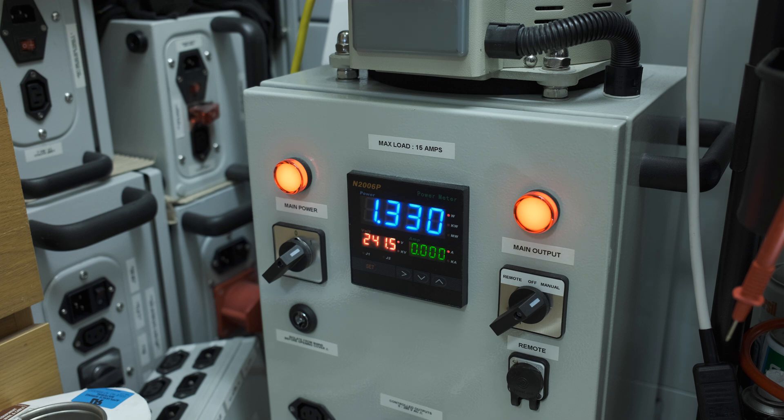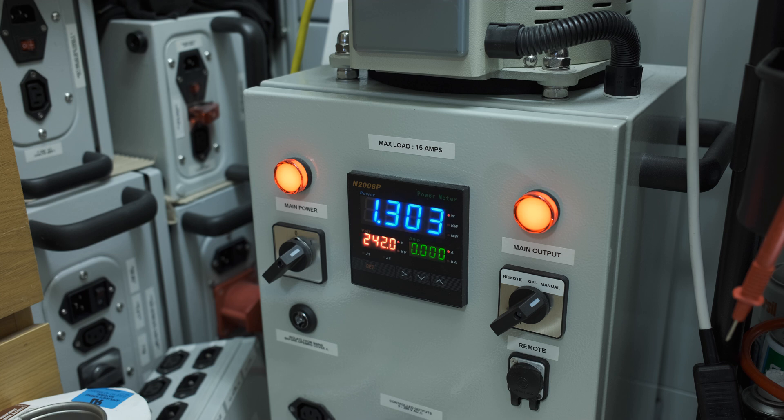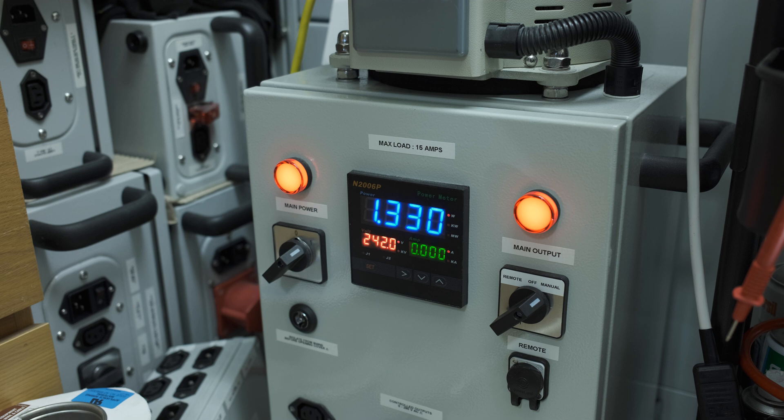Even though technically it should be able to withstand 253 volts. The official spec of UK mains voltage is 230 volts minus 6% and plus 10%, which gives us a range of 216 to 253. So it's technically high but it's within spec, but this doesn't like it.